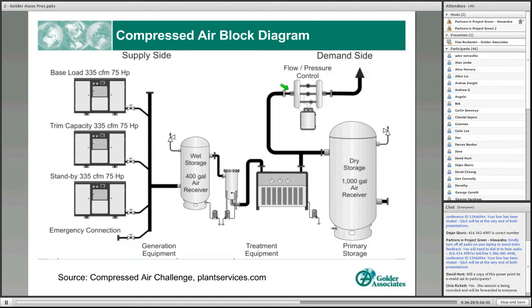An elegant way of dealing with control of the compressed air into the plant is to have a flow pressure control device together with a control system, so that you might even elect to run the compressor plant at a slightly higher pressure upstream of this valve assembly. You might in some cases run the generating plant at 110, 120 psig and then drop it down to a 100 psig or whatever minimum pressure the plant would require. This is an elegant way of allowing you a very fine-tuned control of the compressed air pressure in the plant. With a device like this and the proper control system controlling all three compressors, you could manage or control the pressure on the discharge from the plant at about plus or minus 1 or 2 psig, which is an elegant way of delivering air in a cost-effective way.